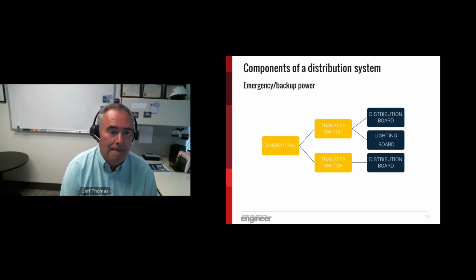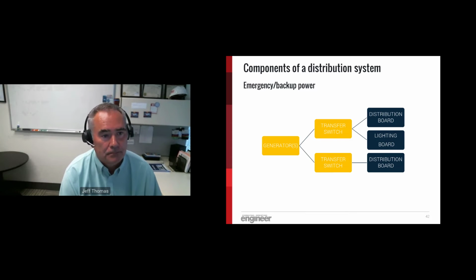And then we have emergency power. Emergency power is conventionally based on a generator, either natural gas or diesel. We'd have some transfer switches. The transfer switches would then take over and feed various distribution boards or lighting boards, depending on our installation. This is a gross oversimplification of an emergency power system. Depending on your facility, this thing can be this simple or extremely complex. Especially in healthcare, NFPA 99, Chapter 6, talks about how this has to play and how it has to be broken up. So again, if you're in the healthcare space, by all means, get familiar with 99. The National Electric Code also talks about components of an electrical emergency system as well.